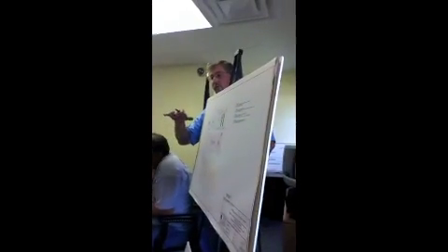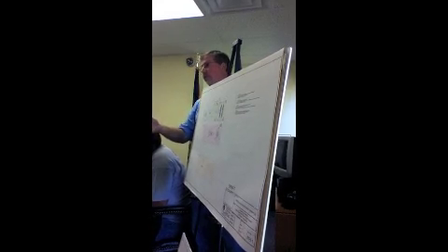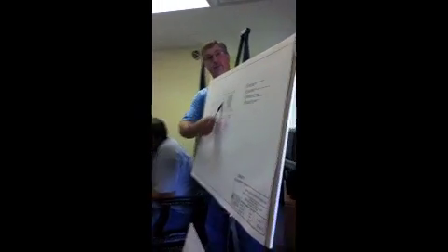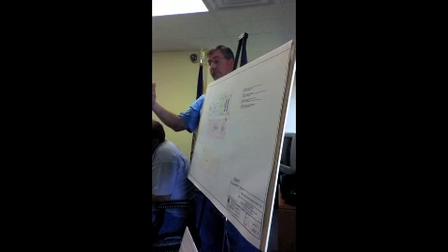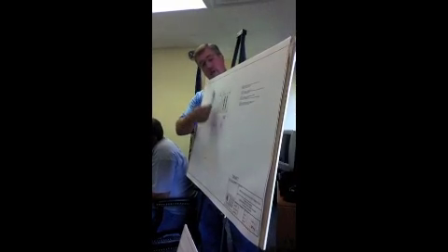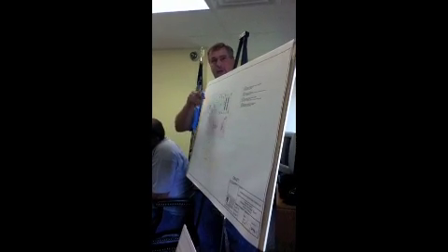You sure? Yes, right now he is showing flows on average during dry weather, no sump pump use, I&I, which is inflow infiltration. He's showing flows of typically, Shane, what, 25, 30,000 gallons? That's what he would see continuously through here. Once he gets a rain set coming on, because of the micro units, his flows triple. He's starting to see 60, 70. So yes, that will eliminate that. And then you can put in more bathrooms, this will allow you into this sewer system. Right now you can't expand. Exactly. Right now you can't expand because of the inflow.